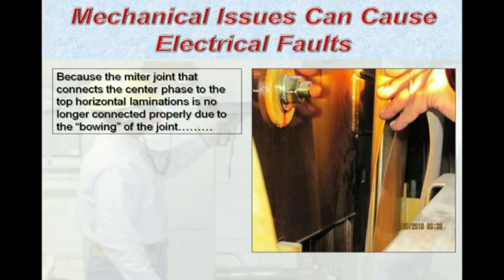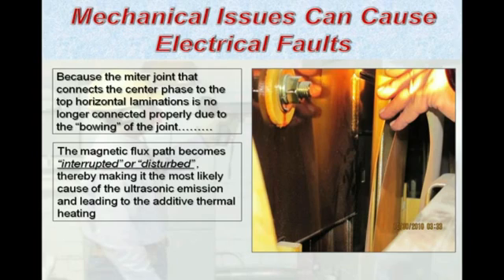Because this miter joint that connects the center phase to the top horizontal laminations is no longer connected properly, based upon this image I showed you earlier, where there's an overlap and a bowing of that joint, it can no longer contain the magnetic flux path, and it interrupts and disturbs it, and this would become the most likely cause of both the ultrasound and the additive heating effects. If you cannot contain the lines of flux within the core, you will get these effects, and both technologies can and do point this out, but without the benefit of the Ultra Probe, this may have gone unnoticed, but thankfully it was found.